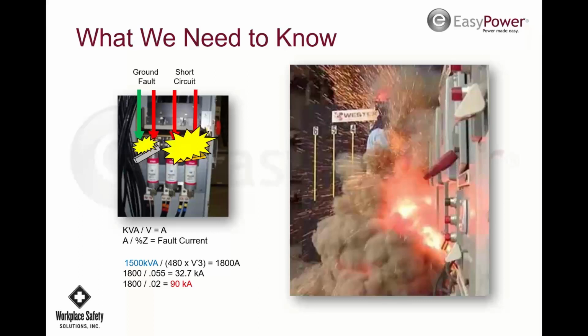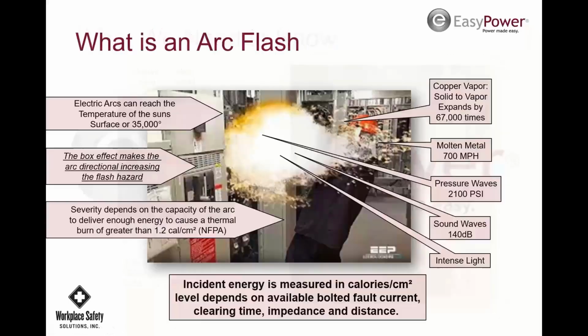Yeah, and so there's a follow-on from Chuck. Okay. Will you be talking about the Z impedance fault, where you have listed on fault current, where the Z impedance value comes from? Yeah, actually the impedance is, let me go back here. So this is actually one of the things that was on here, and maybe that's why it was brought up, because I did list impedance and distance. Distance is your friend when it comes to arc flash. The further out you are, the more significant the drop is. So one example, we had an arc flash level of 101 calories. 3 feet out from that, it dropped to 35. So that's a really good thing to think about.